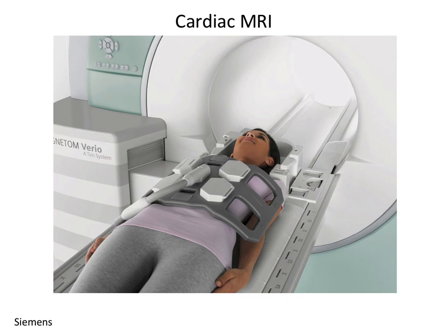And then it goes bang, and it goes into the magnet at great velocity, sticks to the side, and then you have to go in there, anchor a winch to the wall, and winch it out of there. It's thousands of pounds. Sometimes you can winch it out. Sometimes you can't. You have to crash the magnet, quench the field, and then you're in big trouble. So the major hazard of MR is flying metallic objects. I think about 5 fatalities over the whole history of MR. It's not that many, but it's enough to get your attention.